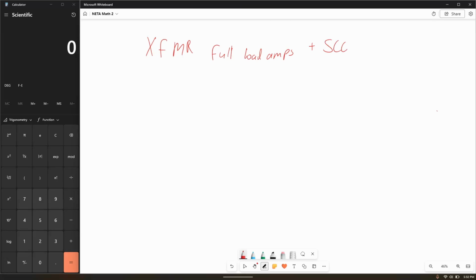circuit current. So what I'm going to give you is a nameplate. The amount of energy a transformer can produce, the amount of current on the low side, is sort of independent of whether it's a capacitive load, a reactive load, or a resistive load. So it's generally given in kVA, in apparent power. We're going to have a voltage rating. In this case, it'll be 15 kV, 15,000 volts on the high side, to 480/277 on the low side. And then somewhere on the nameplate, it's also going to have an impedance, a percentage impedance.